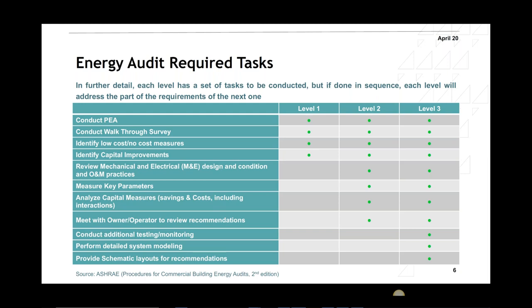Now with the level two, you do exactly what you've done for the level one, plus you need to review the mechanical and electrical design, condition, and O&M practice, so you do more detailed analysis. You would need to do measurements. So you need to do measurements on, let's say, electrical power consumption for the chiller. What is the kilowatt per ton for the chiller? You look at the fans, what is the watt per liter per second? What is the amount of fresh air flow, or outside air flow, going into the building? What is the amount of exhaust flow?